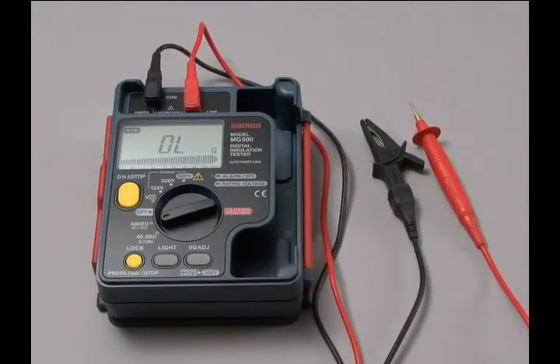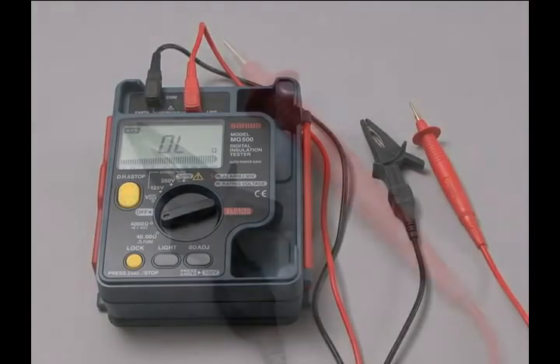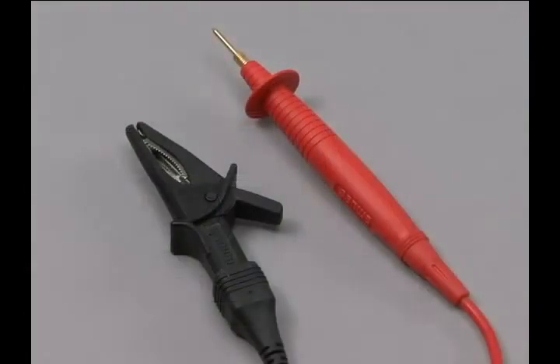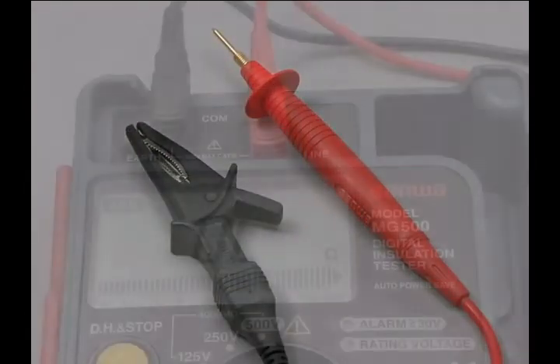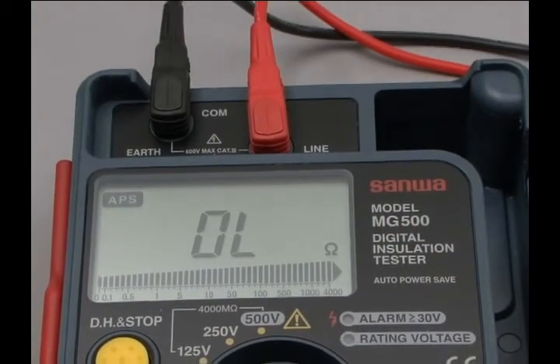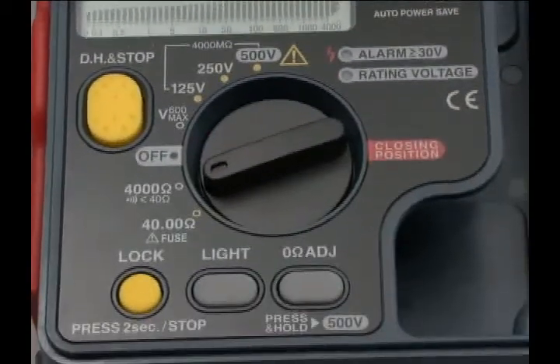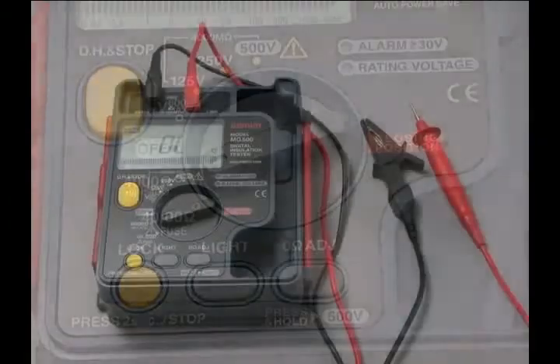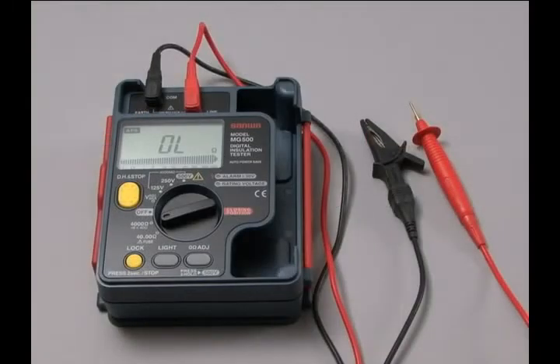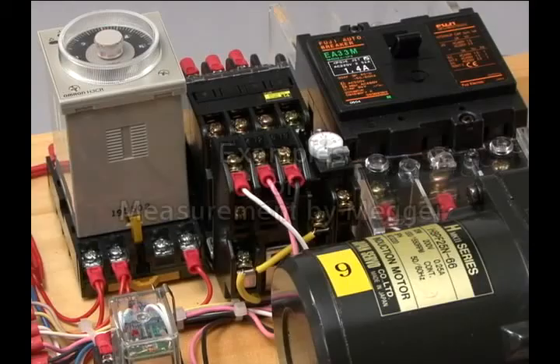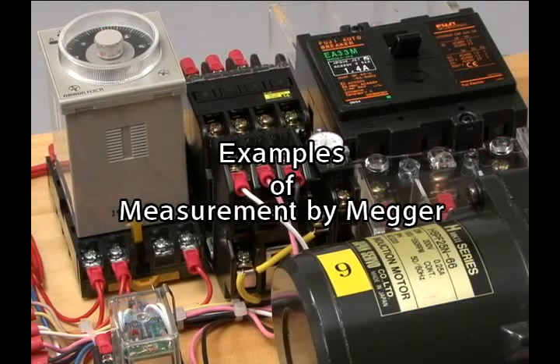The insulation resistance tester is commonly known as a megger. Electric equipment is made shockproof by covering electric cables with an insulating material like vinyl. However, since both humidity and temperature inside ships tend to be high, insulating materials are liable to deteriorate. The risk of electric shock increases if insulation resistance between the coil inside the motor and the case is reduced. As such, insulation resistance between the motor and the case should be measured at regular intervals.